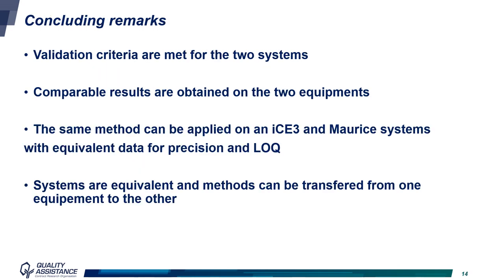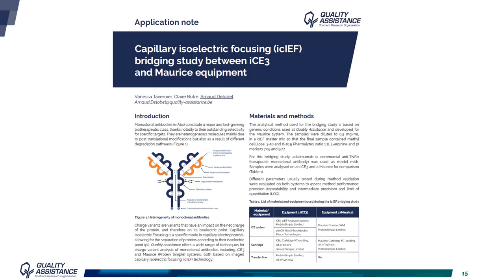To conclude, acceptance criteria are met for both systems individually, indicating that the method would be validated on each system. Furthermore, we obtained comparable results on the two systems — iCE3 and Maurice — indicating that the same method can be applied on both systems, leading to equivalent precision and limit of quantitation. This means that methods can easily be transferred from one system to the other. This work is described and detailed in an application note that can be downloaded on our website.